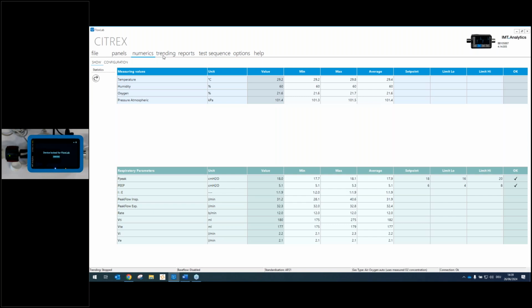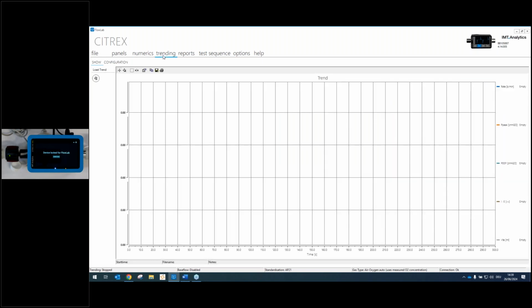In addition to that, you can do trending for up to 100 hours if you use our software on your PC, connected to the H5. So if you have a ventilator that's giving you problems that's intermittent and you want to run it over a day or several days, you can hook up the H5 and use FlowLab to trend that for, as I said, up to 100 hours.